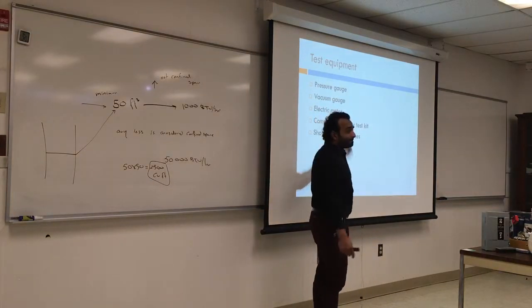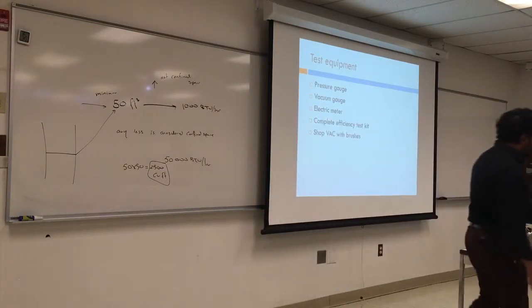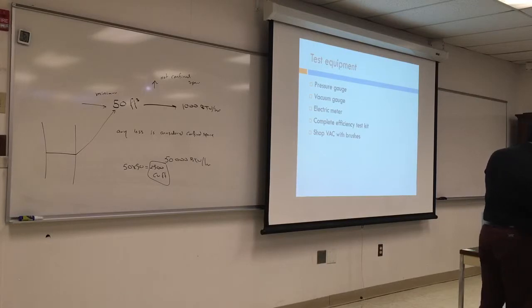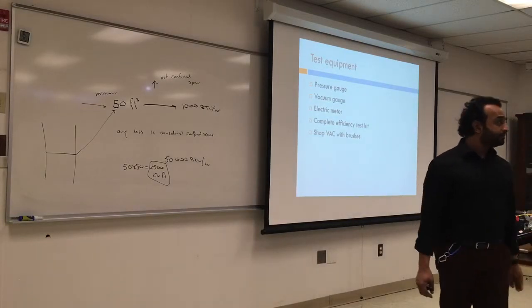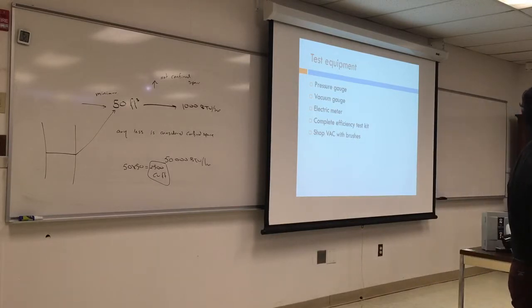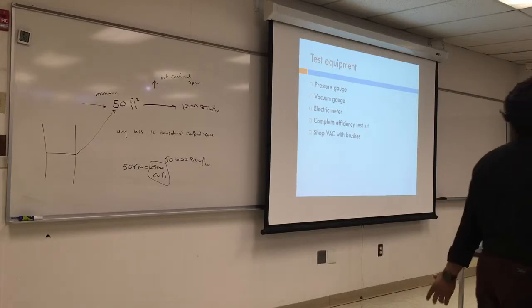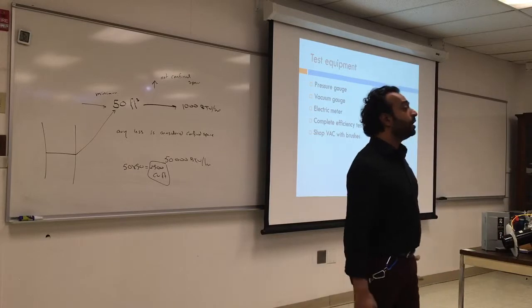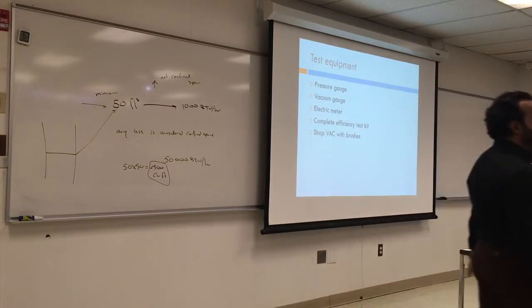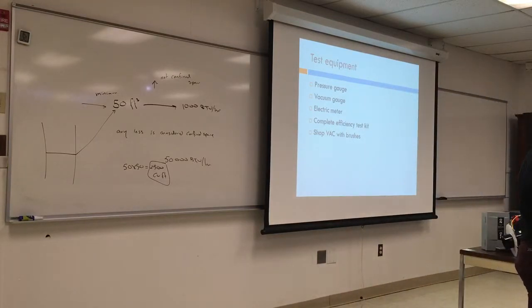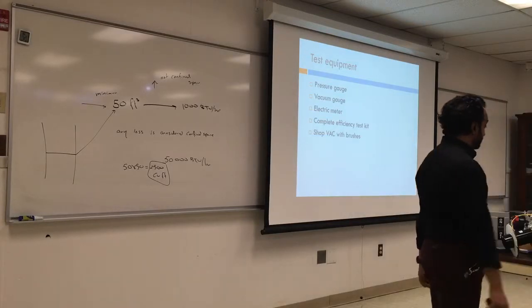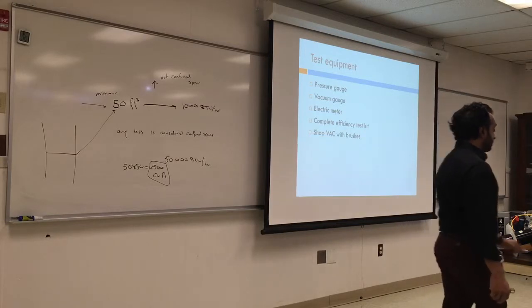A vacuum gauge is going to be in inches, and you put that in the inlet of the pump, where the oil line is. What is the purpose of the vacuum? It's not to vacuum out the air or oil. It will tell you how much suction the pump has based on the oil line. And there's a formula in the book that tells you how much vacuum you need for that pump, how much suction it has to have to pull the oil all the way from the tank to the pump.